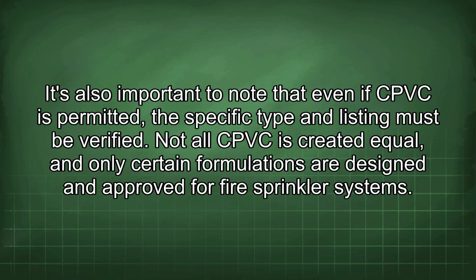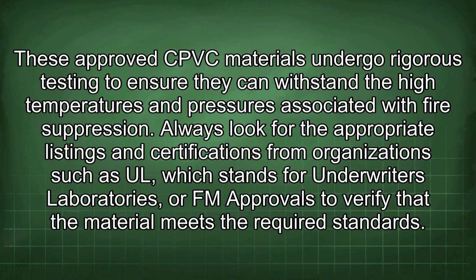It's also important to note that even if CPVC is permitted, the specific type and listing must be verified. Not all CPVC is created equal, and only certain formulations are designed and approved for fire sprinkler systems. These approved CPVC materials undergo rigorous testing to ensure they can withstand the high temperatures and pressures associated with fire suppression. Always look for the appropriate listings and certifications from organizations such as UL, which stands for Underwriters Laboratories, or FM approvals to verify that the material meets the required standards.